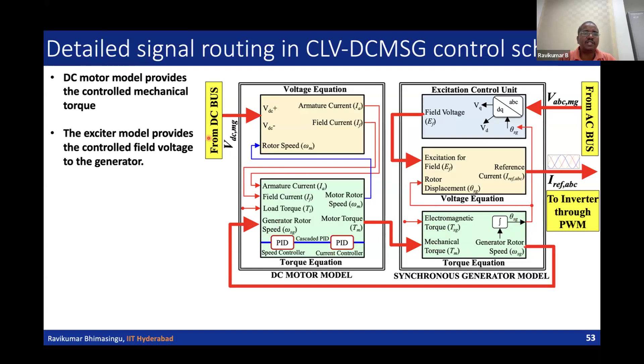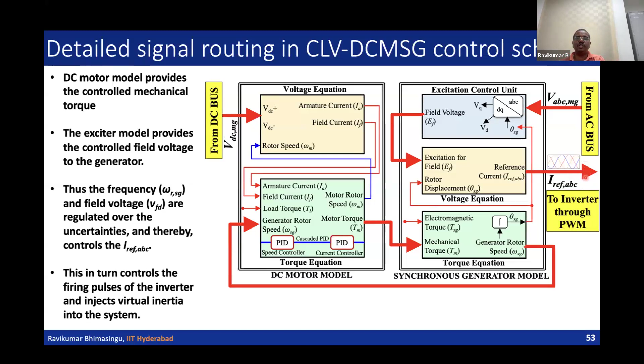Thus the frequency variations and voltage variations are regulated over the uncertainties, thereby controlling the I reference, since this is fed to the inverter to control the pulses. This varies the output inverter voltage and frequency, thus controlling the firing pulses of the inverter and injecting virtual inertia into the system. Since these power electronics based converters lack inertia, by using this control system we can inject virtual inertia into the system.